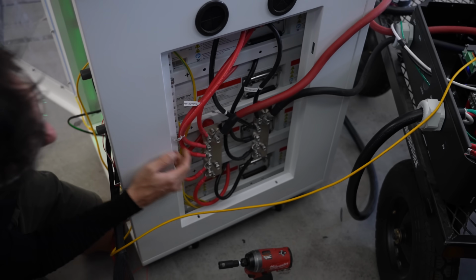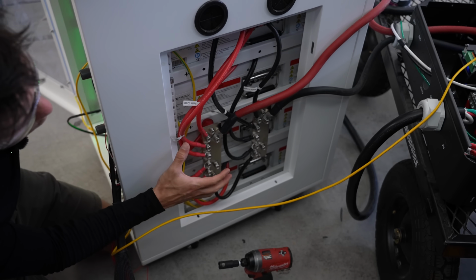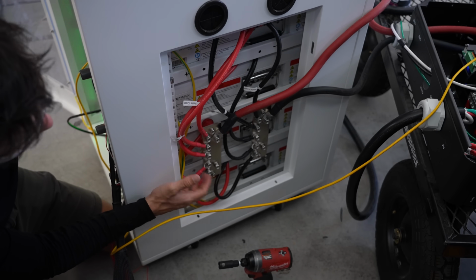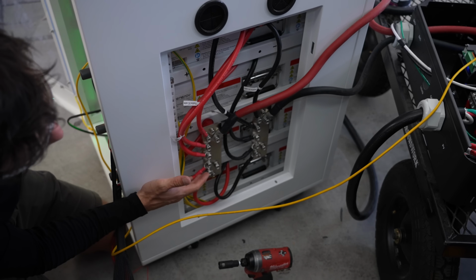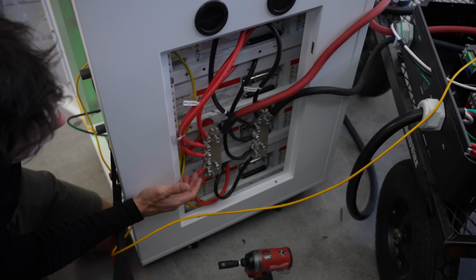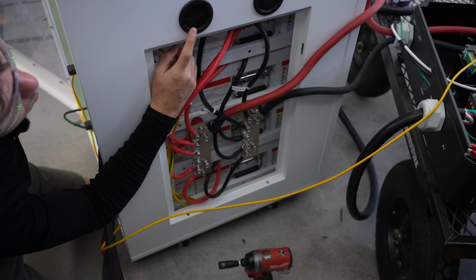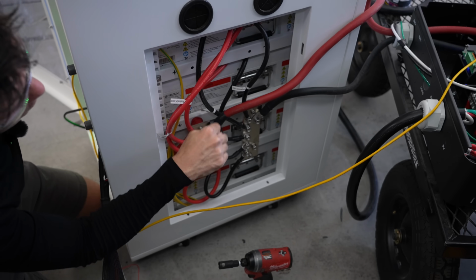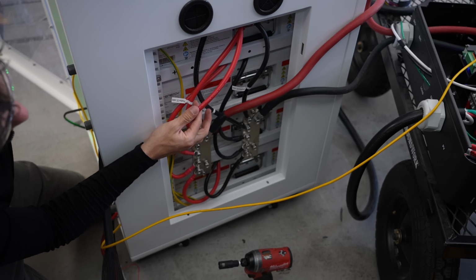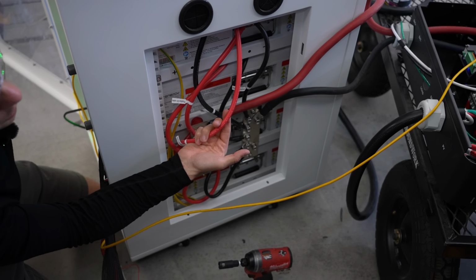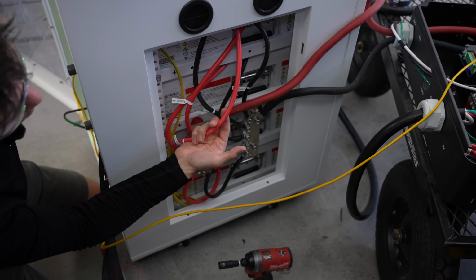On the side of the case, you have the bus bars, and this is how all the batteries connect to the inverter. You need to be very careful working in here because it could cause a nasty short. On the top, you have the holes, and this is where you route your supply conductors down to the bus bar. What's nice about the bus bar is because there's equal length conductors, you won't have any current sharing issues.